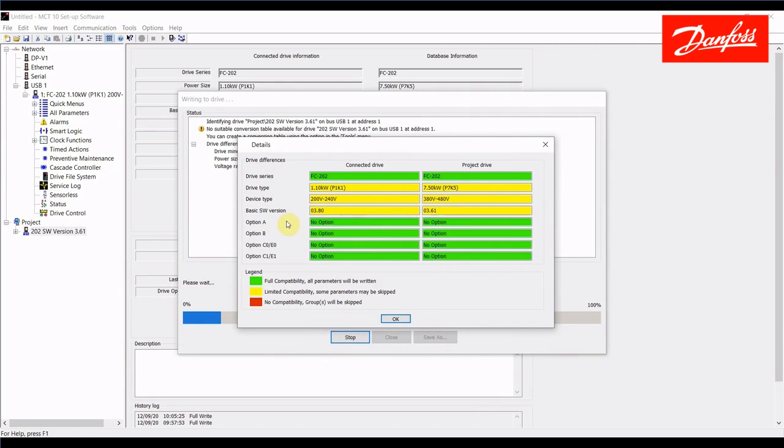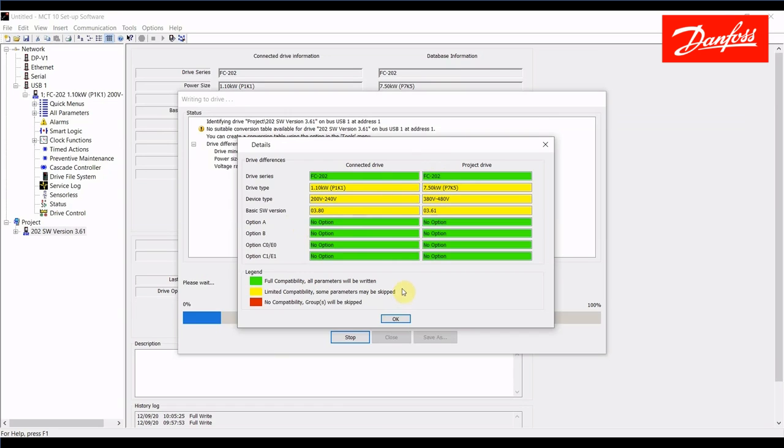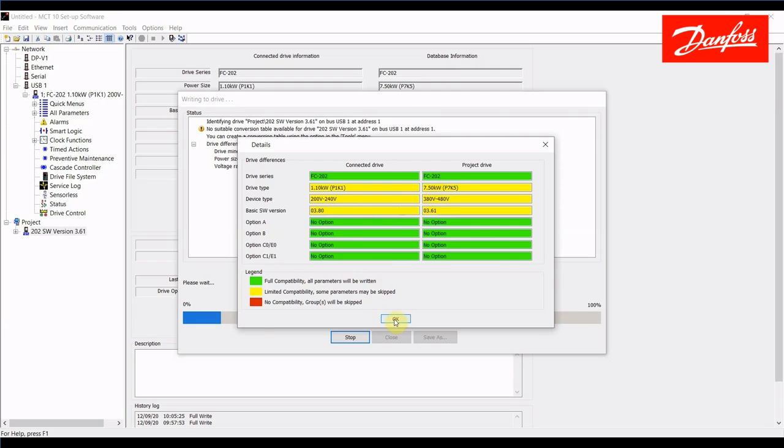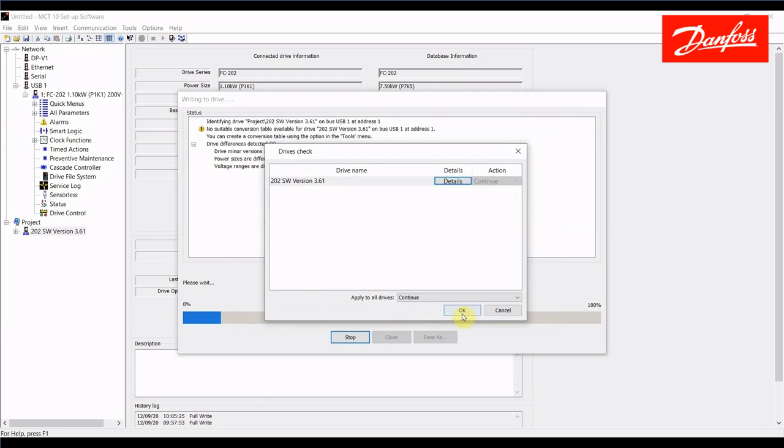Everything in green is fully compatible. This is talking about the option parameters in the A, B and C slot. That's fully compatible because neither of these drives have options so they're really not applicable. The drive series are both 202 so that's fully compatible. But the parameters with limited compatibility here are related to the power size of the drives that do not match, the input voltage of the drives that do not match, and also the basic software version. Again, this is a current version 3.8 I'm trying to write to. So I'm going to say OK with that and press the OK button here and it's going to execute the write.